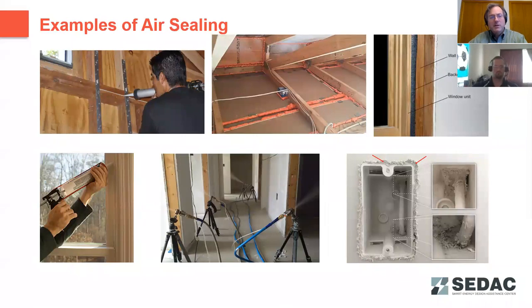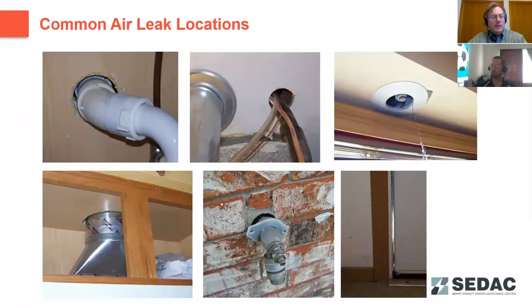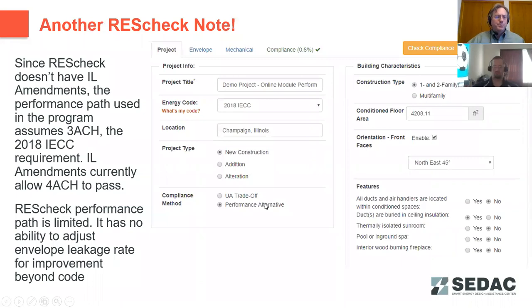So many ways that you can do this: caulking, sealants, foams, going around and making sure wherever we have dissimilar materials or 2 similar materials coming together. On the left there, you can see where 2 boards come together. There's a joint between there, and making sure that we seal all of those up. So many different common leak locations around piping, recessed cans in soffits and kitchens. That's a large one for a previous area.